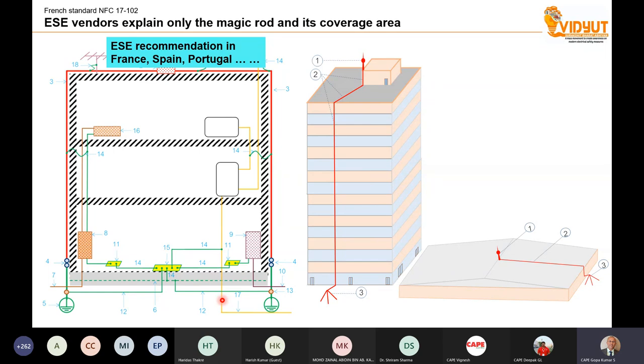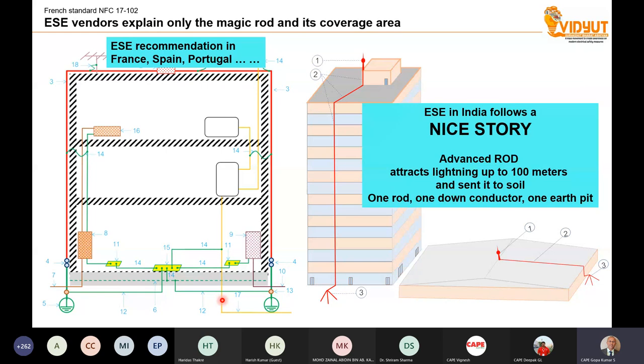People say you have a rod, a simple rod, an advanced modern rod. It attracts lightning from 100 meters and sends it to ground without disturbing your building. So ESE in India generally follows a nice story. When you listen to the story, it looks very good. Aha, 100 meters. So this advanced rod attracts lightning up to 100 meters and sends it to soil. And this is the story which is explained in India. One rod, one down conductor, and one earth pit.